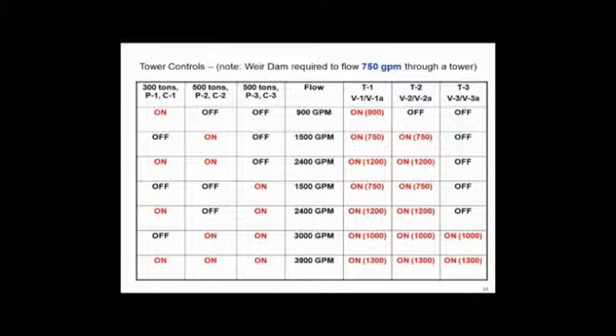Well, in this case, I looked at having T1 and T2 on line, which would give me what? 1200 GPM per cell. I've got T3 off. And is that an acceptable operating condition? Absolutely. It's more than 750, below the 1500. That's fine. You can tell your control man, that's a great place to run. What else could you do here? What's another option?